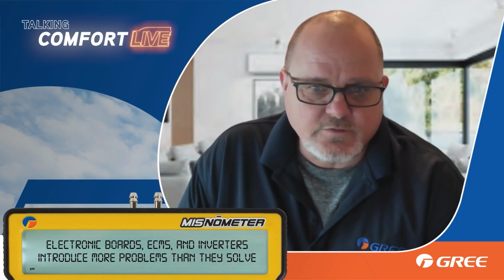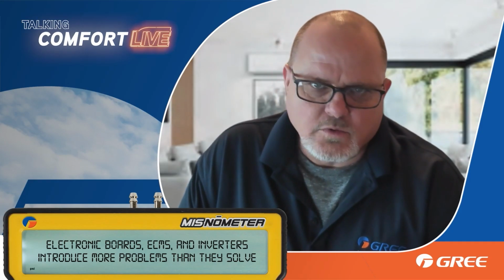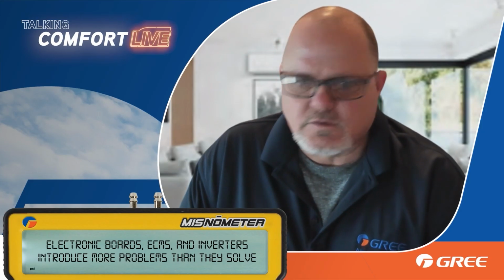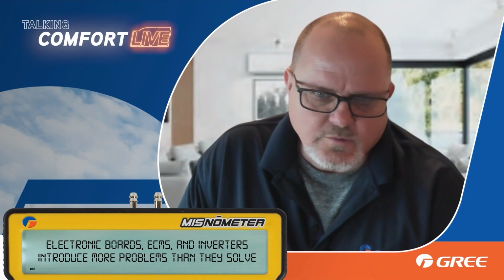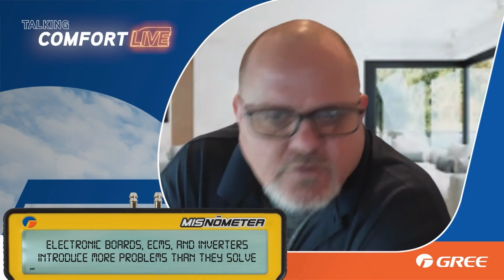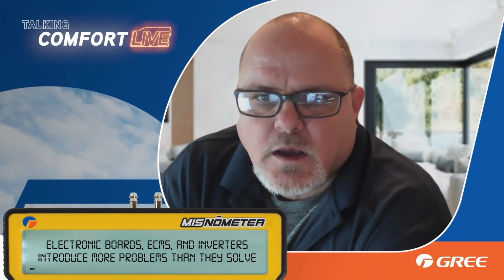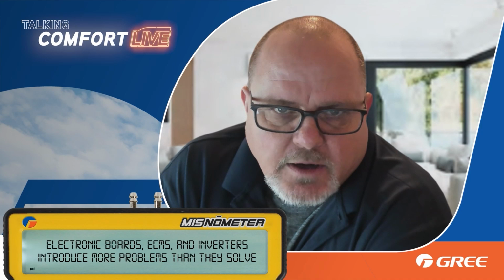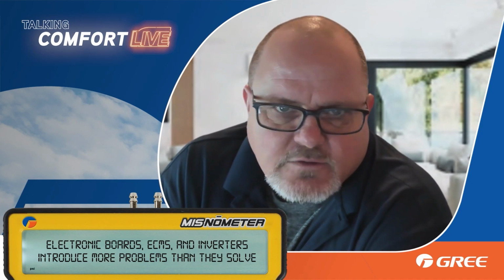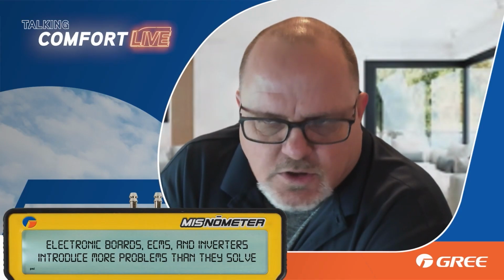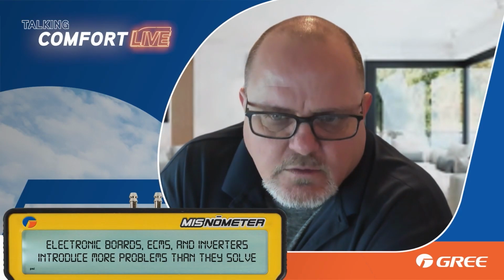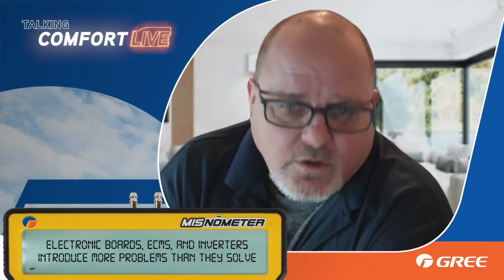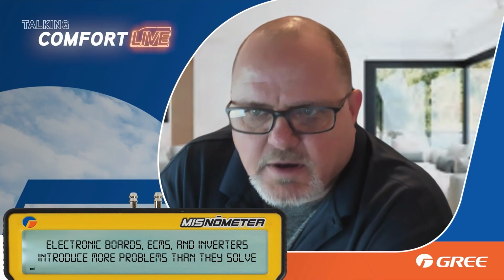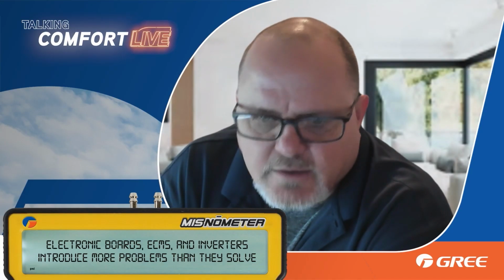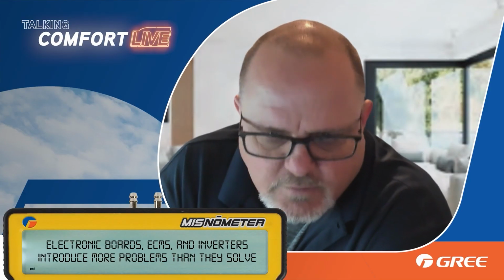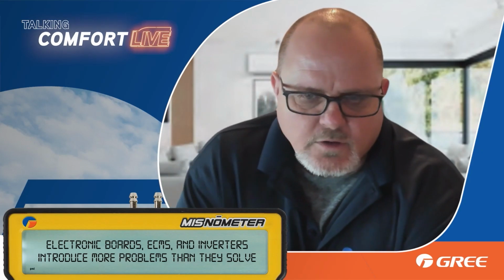Almost every HVAC service technician out there is very comfortable with working with standard technology that uses a permanent split capacitor compressor, what it was referred to when I went to trade school, because there was a run capacitor in the circuit at all times. Now, whether or not that machine has a start capacitor added to it depends on the machine and manufacturing, or if a start kit was added. But I think they're very comfortable with start capacitors, run capacitors, contactors, standard equipment that's been built for as long as I've been in this business, over 30 years.